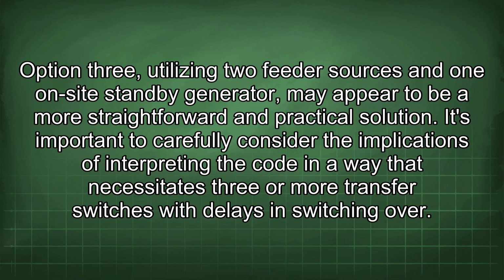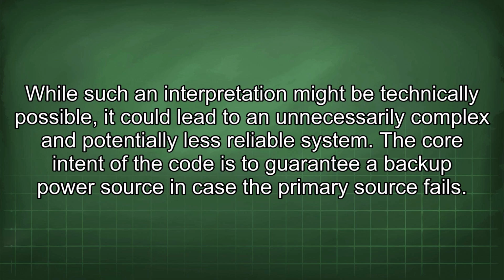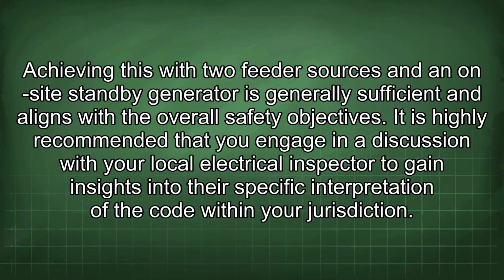It's important to carefully consider the implications of interpreting the code in a way that necessitates 3 or more transfer switches with delays in switching over. While such an interpretation might be technically possible, it could lead to an unnecessarily complex and potentially less reliable system. The core intent of the code is to guarantee a backup power source in case the primary source fails. Achieving this with 2 feeder sources and an on-site standby generator is generally sufficient and aligns with the overall safety objectives.